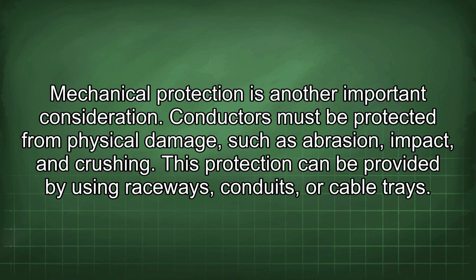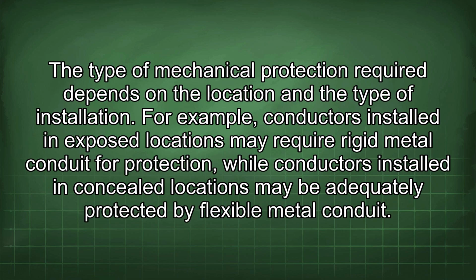Conductors must be protected from physical damage such as abrasion, impact, and crushing. This protection can be provided by using raceways, conduits, or cable trays. The type of mechanical protection required depends on the location and the type of installation. For example, conductors installed in exposed locations may require rigid metal conduit for protection, while conductors installed in concealed locations may be adequately protected by flexible metal conduit.